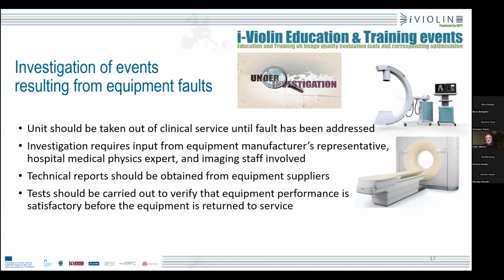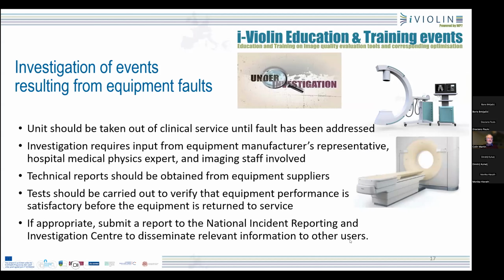So technical reports should be obtained from the equipment suppliers and tests carried out to verify that the equipment performance is satisfactory before the equipment is returned to service. And then, if appropriate, a report might be submitted to the National Incident and Reporting Centre, so that information about that sort of incident or faults can be disseminated to other users.